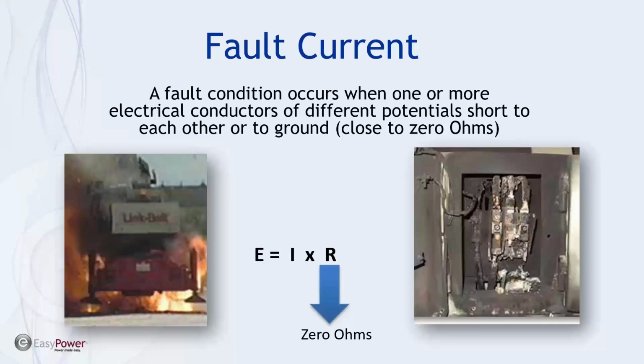And so this is also called available bolted fault current. What I'm doing by saying bolted fault current is meaning I'm bringing the resistance down to 0. So when I bring R down to 0, I, being inversely proportional, should go up proportionally. And if R is at 0, then theoretically I should be an infinite amount. We don't have an infinite amount available, so it becomes all that is available from the system. So that short circuit or that ground fault is going to have the maximum amount of fault current that's available. And that may be 125,000 amps, it may be 10,000, it may be 2,000.